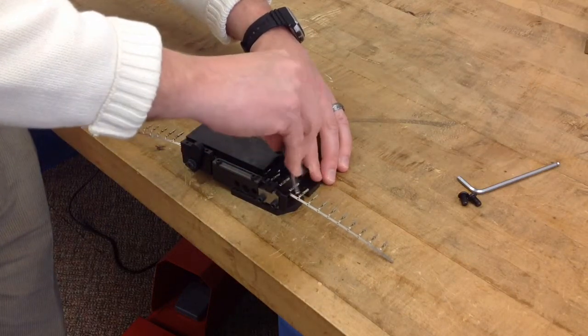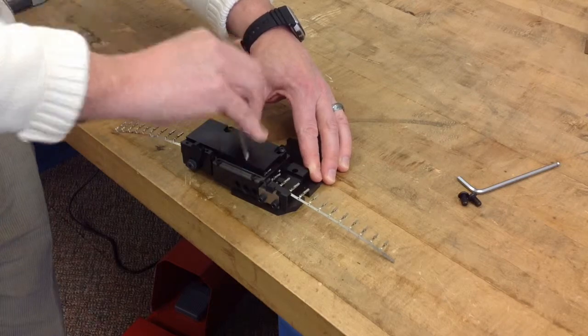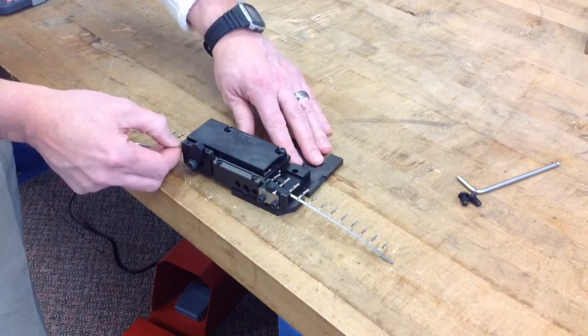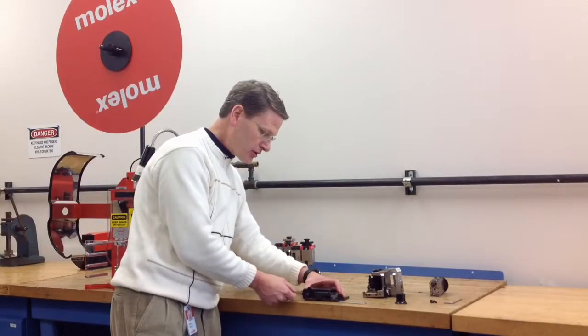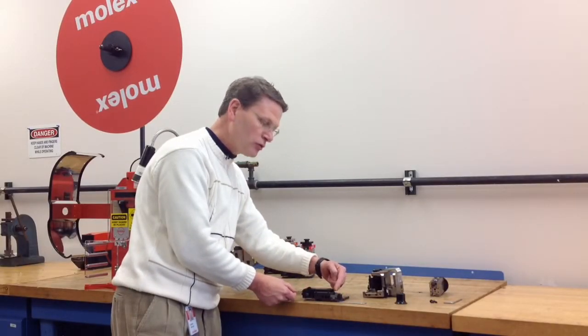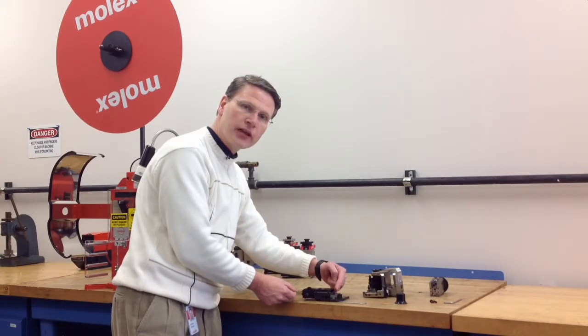And then we want to make sure that that rear cover is still tight against the terminal strip, but it still allows freedom of movement. One way to check is to jiggle the terminals on one end and you shouldn't see them move over the tooling or over the anvils.